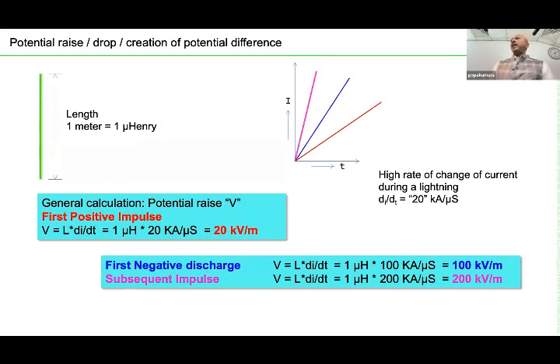What we should understand is, lightning has 2-3 types: positive strike, negative strike, subsequent strike, long duration strike. We will discuss it later. Now, in a subsequent strike, for example, the rate of change of current is very high. The di by dt is very high. Let's say, for example, 200 kiloampere per microsecond. What happens is, once this current flows through a wire, a huge potential gets generated in that wire.